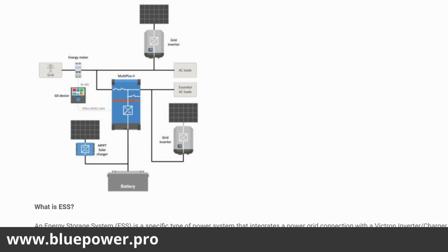On the Victron inverter, we limit it to the feedback of the inverter's capacity. So we can't feed back more than what the inverter can invert. So that's going to be limiting your DC coupled PV feed-in that you can achieve to your non-essentials. But your grid tie inverter can feed in extra power on top of that. So if you've got a 5 kVA inverter, you can invert 5 kilowatts of MPPT charging power to your non-essential loads and still have 5 kilowatts of power from the grid tie inverter feeding your non-essential loads. And then on the left hand side we've got our solar MPPT, the Victron MPPT that is connected onto the system.